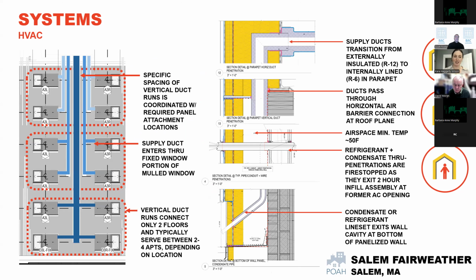Because we're limited by the code complexities of the existing building and its infrastructure, and what it can and cannot support, we're taking one duct all the way down, keeping it local to 2 floors, a second duct down to floors 3 and 4, and then another set of ducts from 4 and 5. This is the most typical pattern we have, though sometimes it's a little atypical, but it lets us serve every single unit with fresh air.